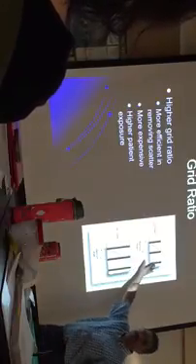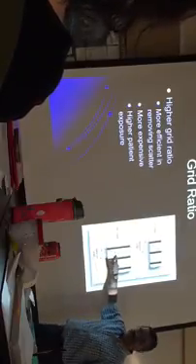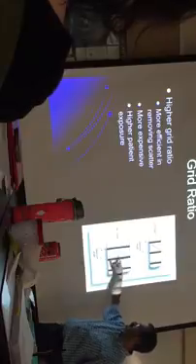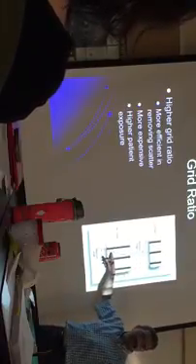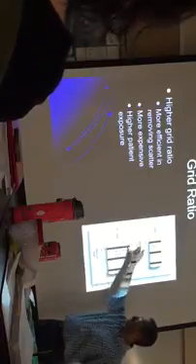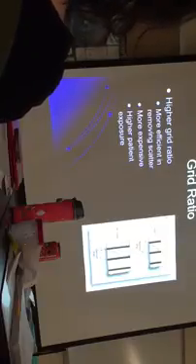All right, now take a look at this. This grid, for example, even though the spacing between lead strips is the same as this one, has double the ratio because they have increased the height. Because think, the purpose of the lead strip here is to absorb scatter radiation, right?